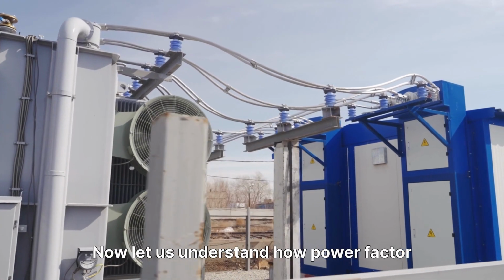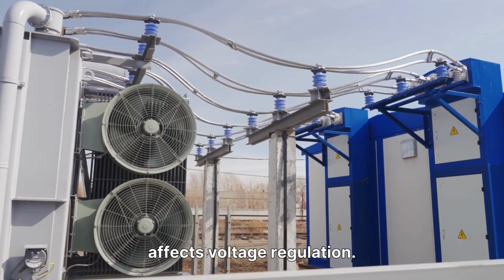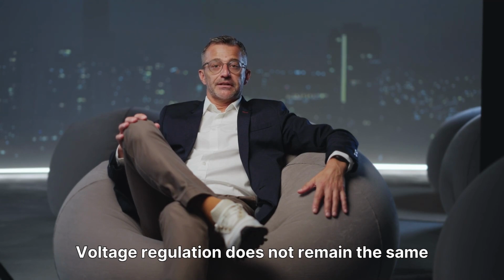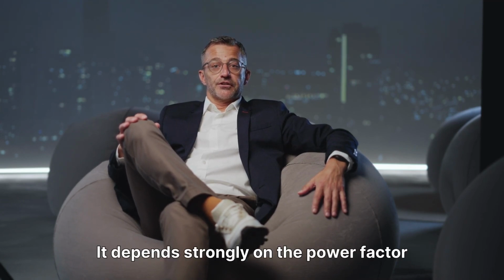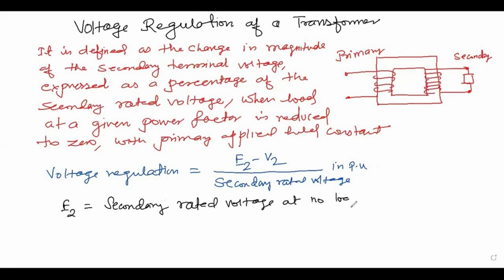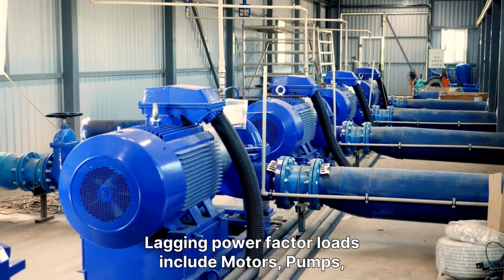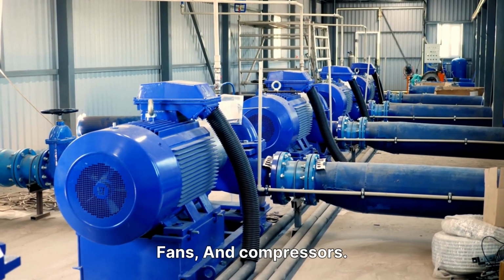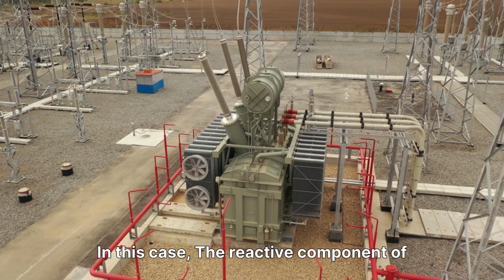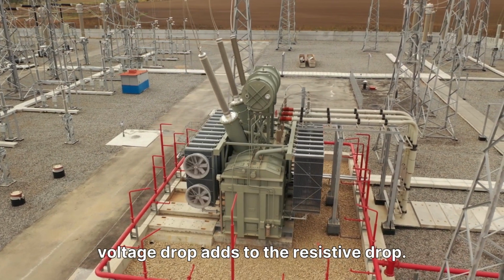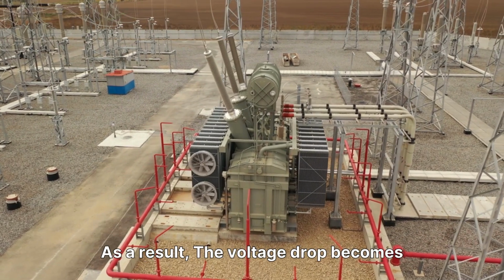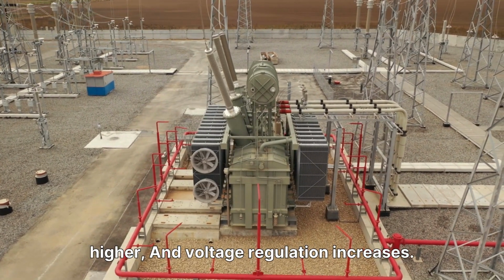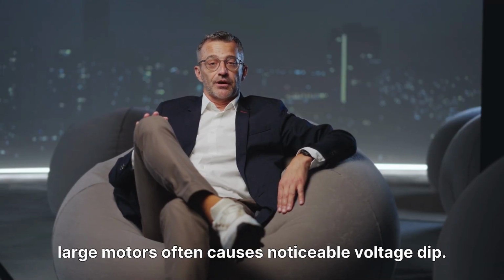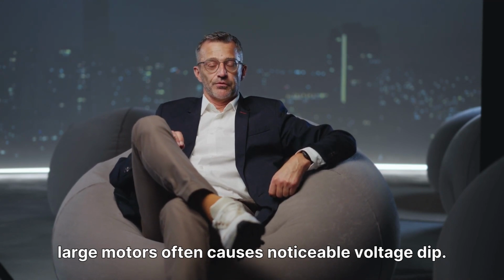Now let us understand how power factor affects voltage regulation. Voltage regulation does not remain the same for all loads. It depends strongly on the power factor of the connected load. Let us first consider a lagging power factor load. Lagging power factor loads include motors, pumps, fans, and compressors. In this case, the reactive component of voltage drop adds to the resistive drop. As a result, the voltage drop becomes higher and voltage regulation increases. That is why in industrial systems, starting large motors often causes noticeable voltage dip.